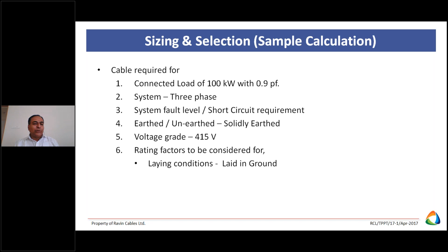Voltage grade is 415 volt. Now, rating factors, what we considered. Let's suppose the ground or environment temperature is 35 degrees centigrade. Then the route length is 210 meters. Then voltage drop is allowed maximum 2.5%.